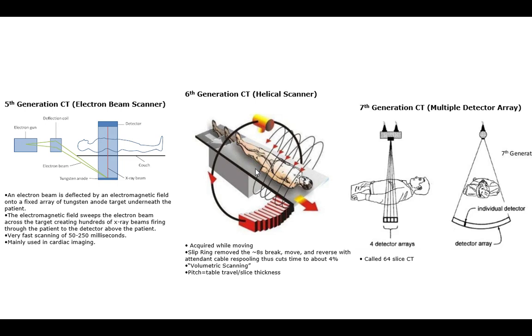Now, just because I have 64 detectors doesn't mean that I'll use 64 parallel planes for reconstruction. Very often they'll group them together, 1 at a time, 2 at a time, 4 at a time, 8 at a time, 16 at a time on the common groupings. And they make a virtual one of these long things. So it's always in a column. You don't ever go the other direction, because if you go the other direction, you blur across objects, right? We're considering that our slices are really axial slices when we build them.